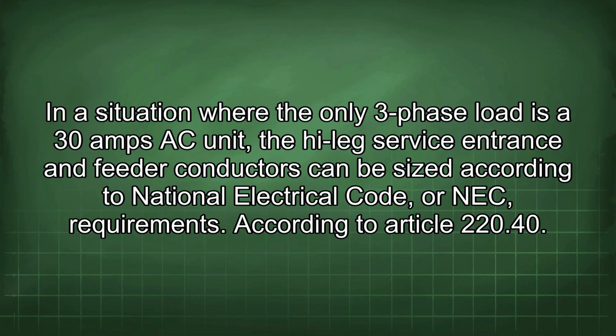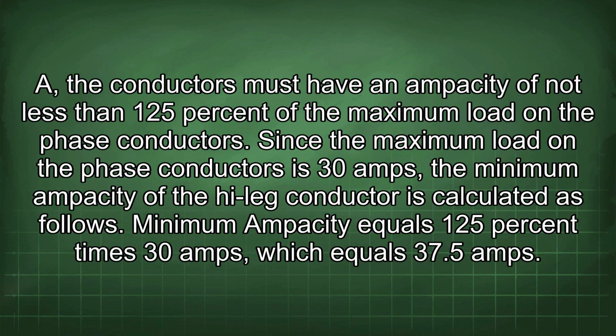In a situation where the only three-phase load is a 30 amps AC unit, the high leg service entrance and feeder conductors can be sized according to National Electrical Code, or NEC, requirements. According to Article 220.40 A, the conductors must have an ampacity of not less than 125% of the maximum load on the phase conductors.